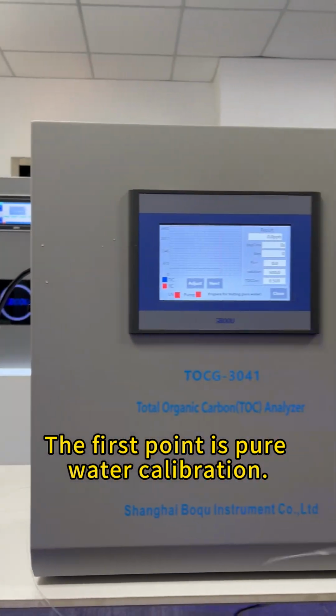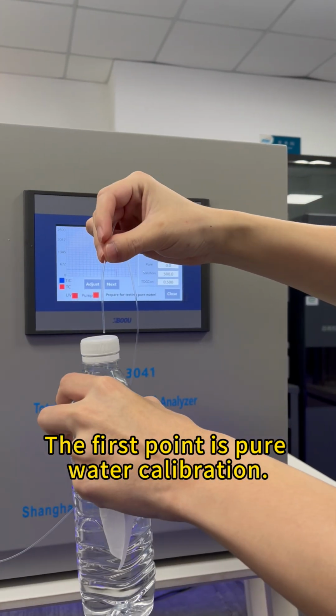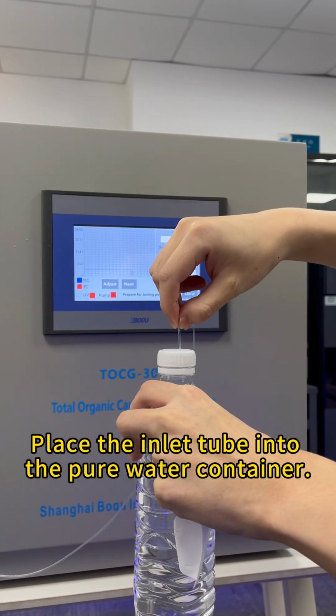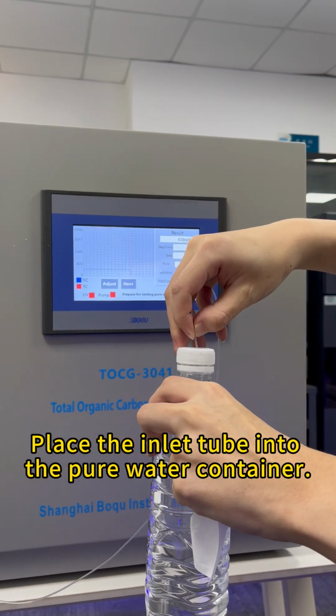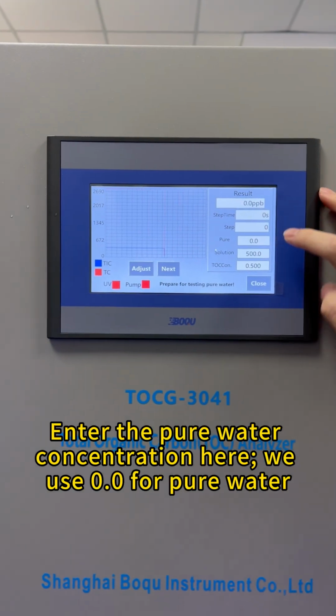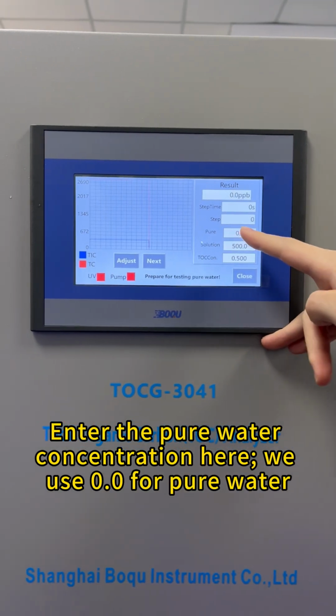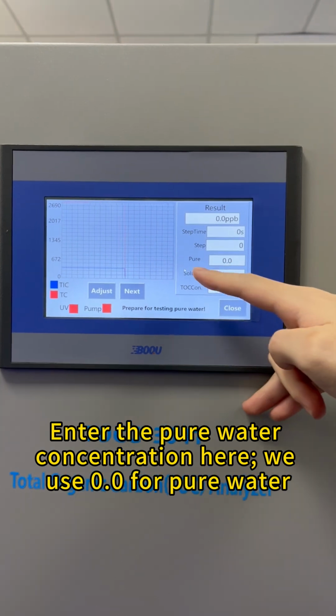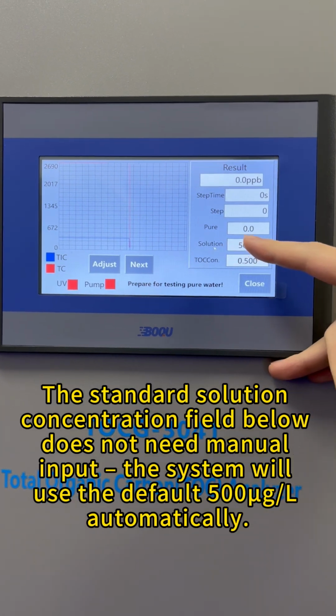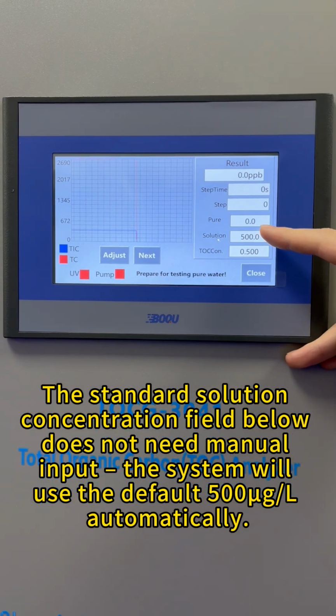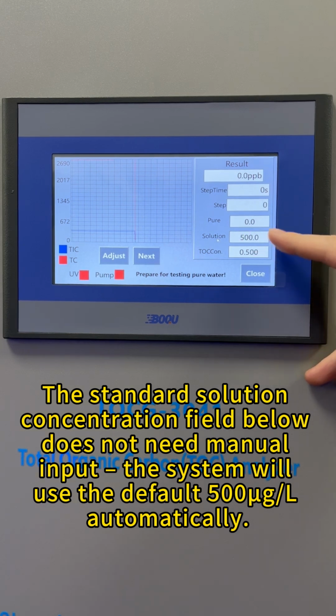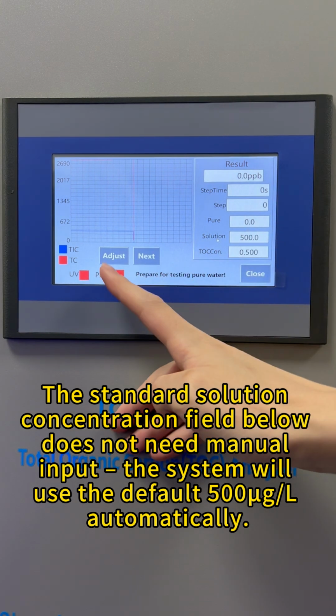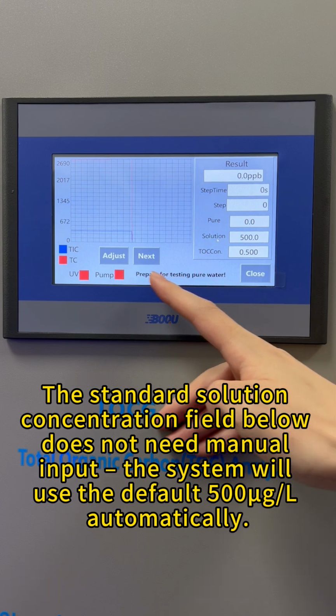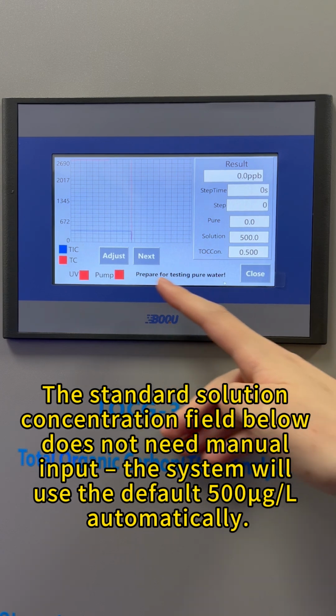The first point is pure water calibration. Place the inlet tube into the pure water container. Enter the pure water concentration here. We use 0.0 for pure water. The standard solution concentration field below does not need manual input. The system will use the default 500 micrograms per liter automatically.